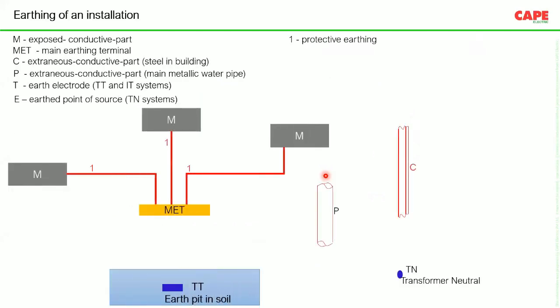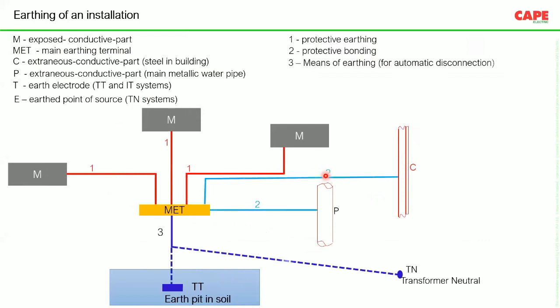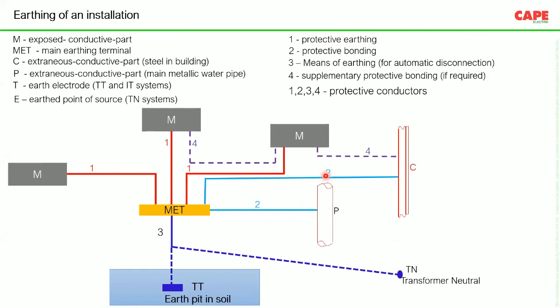As I said, in the National Electrical Code, you can see this particular picture. This picture is explaining protective equipotential bonding. Protective equipotential bonding means all dead metal parts in your building, such as M stands for exposed conductive part, CP, these are some kind of metal installations, extraneous conductive parts. If you go for a TT system, then one building requires one earth connection to an earth pit. MET must be connected to the earth pit at least once. Then if you go for a TN system, the MET has to be connected to the transformer neutral, and this is called protective equipotential bonding.